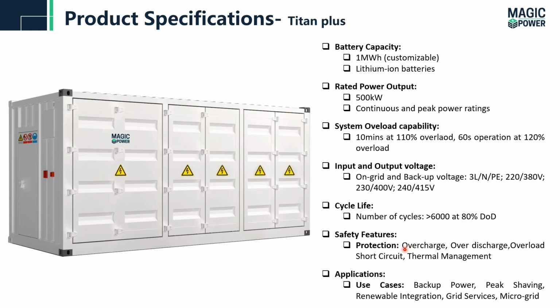Safety features or protections: for the batteries we have overcharge and over-discharge protection. For the load side, it can be overload and short circuit protection, and for the system itself there is thermal management, so there are other integrated protections in the system. Application cases for this energy storage system: it can be used as a microgrid or for grid services. It could be used for backup power, peak shaving, and renewable integration. So basically, the series is an all in one unit.